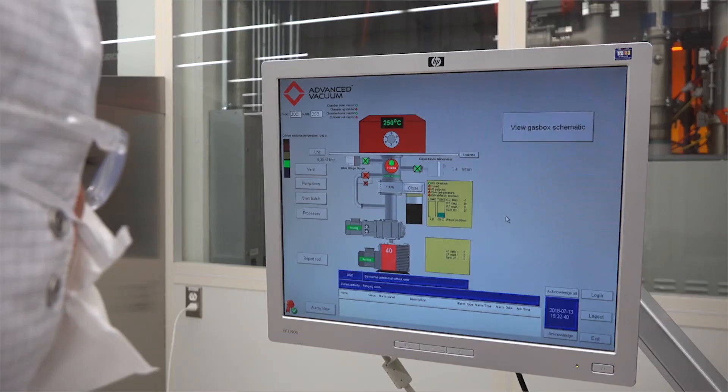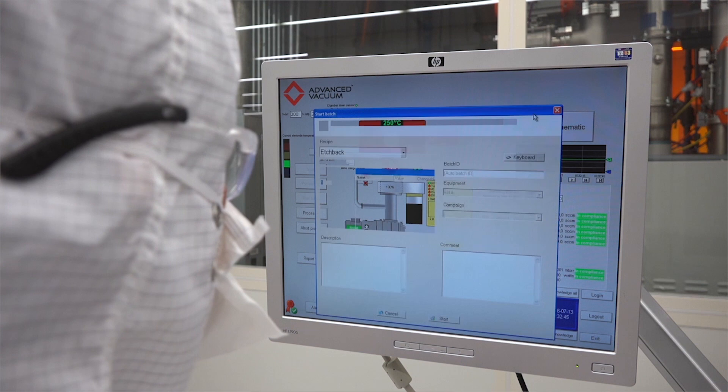we run a special recipe called an etch-back. This process creates a plasma in the system that does not deposit material but rather cleans the chamber. This plasma removes or etches any material we may have just deposited on the walls and the base of the chamber. This cleans the system because we don't know what material the next user will deposit. And our remaining deposited material may contaminate their thin film. Thank you for watching our demonstration of the PECVD deposition system.